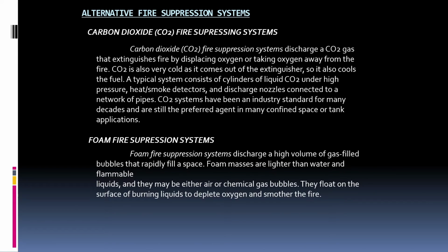Carbon dioxide fire suppression systems. Carbon dioxide fire suppression systems discharge CO2 gas that extinguishes fire by displacing oxygen, or taking oxygen away from the fire. CO2 is also very cold as it comes out of the extinguisher, so it also cools the fuel. A typical system consists of cylinders of liquid CO2 under high pressure, heat or smoke detectors, and discharge nozzles connected to a network of pipes.